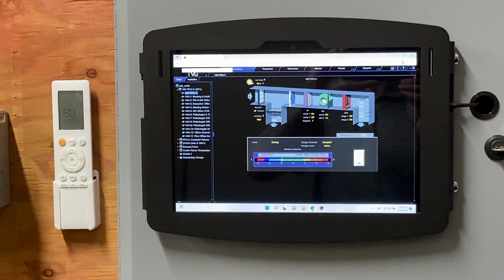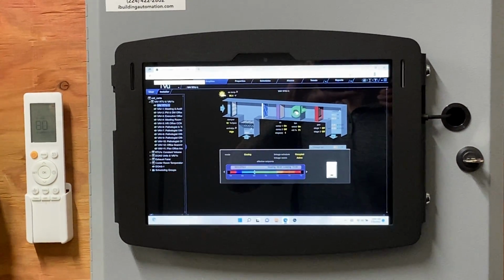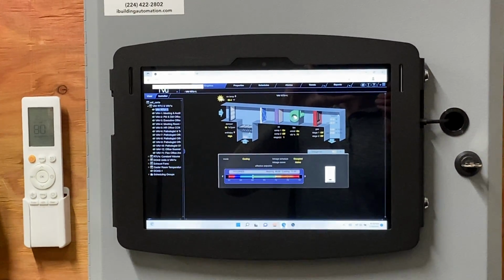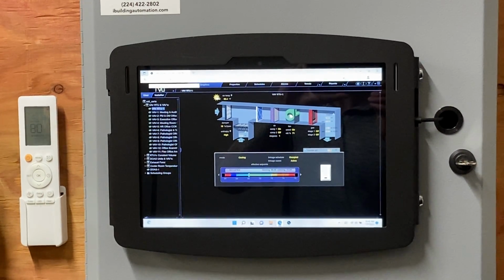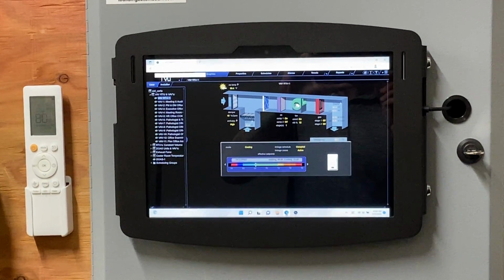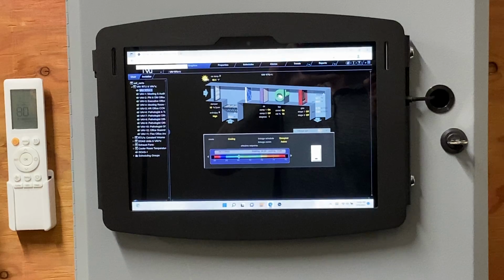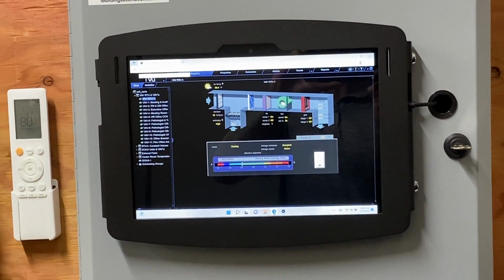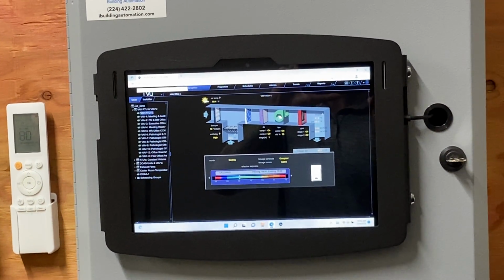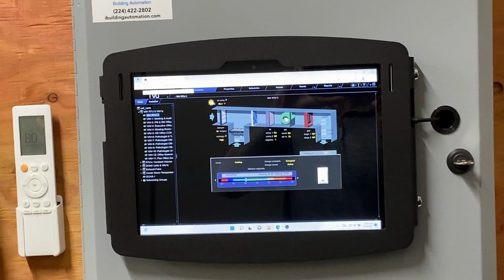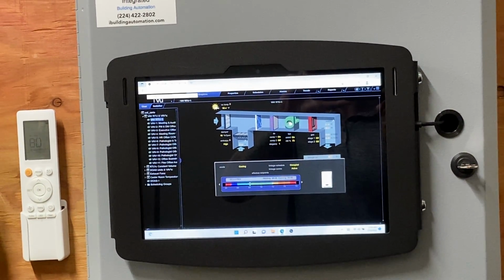So that's just outside air input, that's not going to be space humidity. That's just saying, hey, it's outside - if it's above 45, you're not going to use outside air to modulate. We're not controlling humidity in the space with that. That value is just for outside air. But you can definitely set it so the rooms are within a certain range.